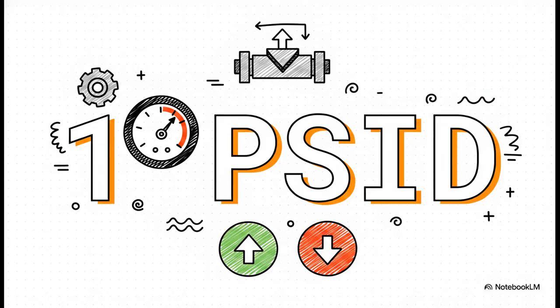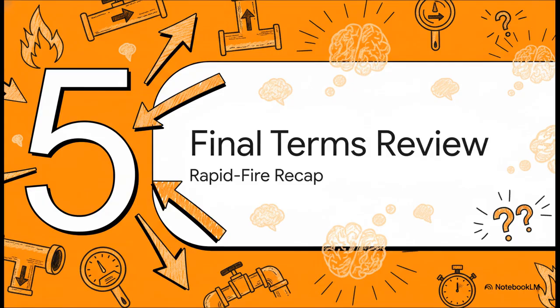And what's the magic number you're looking for? Burn this into your brain for the test. The check valve has to hold at least 1 pound per square inch of differential pressure, 1 PSID. If your gauge reads 1 or higher, it passes. If it's anything less than 1, it fails. It is that simple.